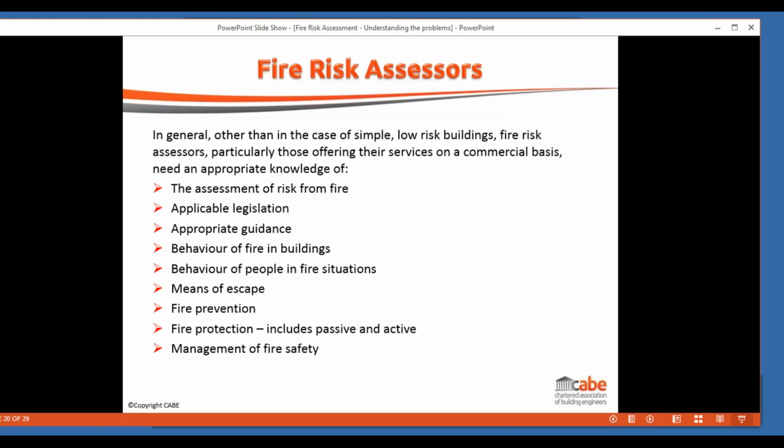It could be a landlord, a managing agent, or a residents association. And increasingly people are saying, how can I effectively do a risk assessment of the common parts of a block of flats if I don't know what's going on the other side of that fire door? So at the flat entrance door, if somebody's put a motorbike in their flat hallway, it's potentially going to have a knock-on effect. Although we've got a degree of protection by the fire door itself, there is an argument that you can't effectively control the risk in the common area if you don't know what's going on behind the fire doors.